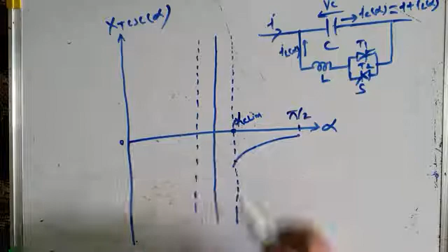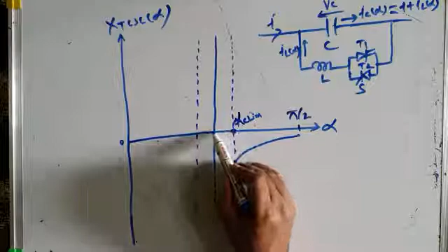At alpha equal to alpha C lim, it has maximum capacitive reactance, and if you operate it below alpha C lim, at this point resonance occurs. When resonance occurs, XL alpha is exactly equal to XC, and the capacitive reactance becomes infinite, not current. Capacitive reactance tends towards infinity. So it's not advisable to operate your TCSC for a delay angle below alpha C lim, because as you decrease your delay angle of TCR below alpha C lim, you are reaching very close to the resonance condition, where XL alpha is equal to XC and TCSC reactance tends to become infinite.